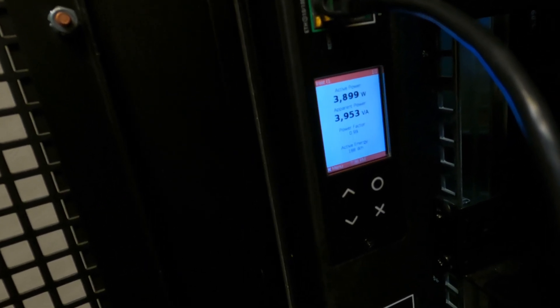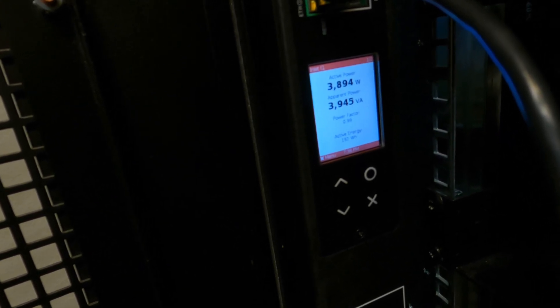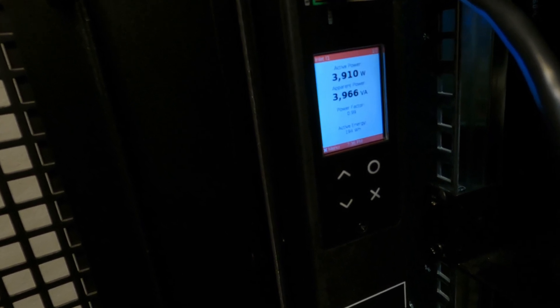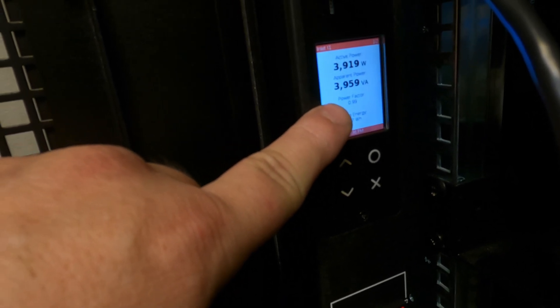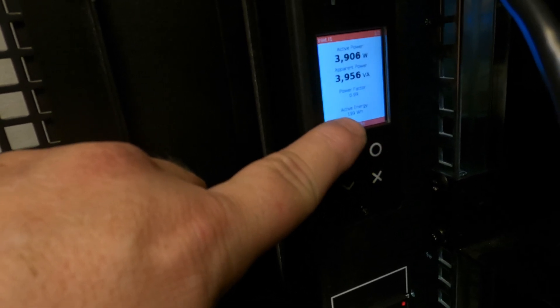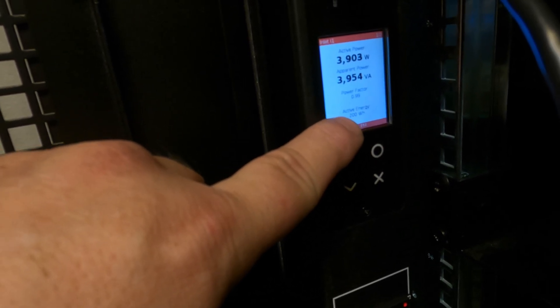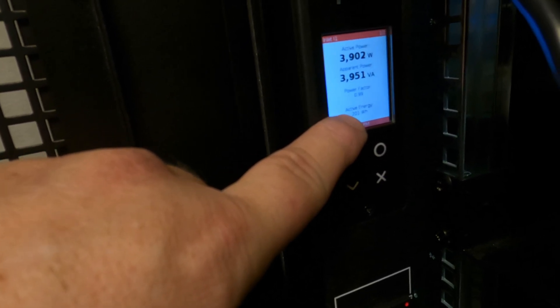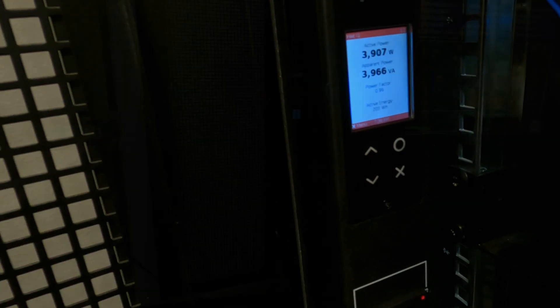Oh, I gotta take those slugs off. There we go. Now you can see it much better. And it gives you the current active power, which is kilowatt hours and apparent power. Power factor now is so much better. We're at 0.99 and active energy, it's counting up the kilowatt hours already. We just gotta update the time on this. That's it.